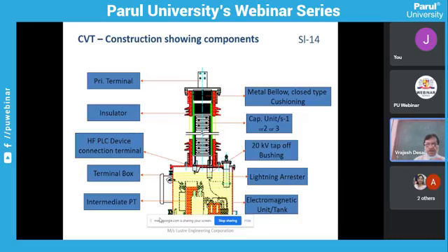Now, coming to the detailed cross-sectional view, on the top side you can see the primary terminal. Then you have an insulator as an external insulation. Then this HF PLC device connection terminal. This terminal is used for power line carrier communication purpose. And we have a terminal box where all the secondary output terminals are located. What you see inside is the intermediate PT. The detail of this I will show you through schematics. Then on the right side, a metal bellow which is provided for compensation because it is oil filled.